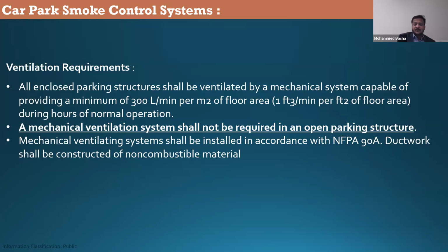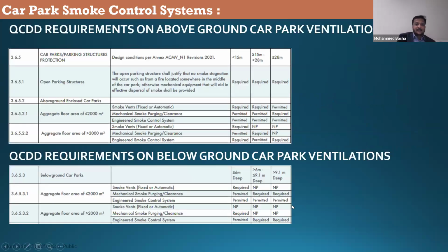Mechanical ventilating system ductwork shall be in accordance with NFPA 90A. Ductwork shall be of non-combustible material. Okay. You can see these are the QCDD requirements. Above ground car parks, open car parks. The open car park shall justify that no smoke stagnation will occur, such as from a fire located somewhere in the middle of the car park. Otherwise, mechanical equipment that will aid in effective dispersal of smoke shall be provided. For open car parks, you do not need to provide a smoke ventilation system, but if civil defense asks you to prove, you have to do an analysis to prove that there is no smoke stagnation.